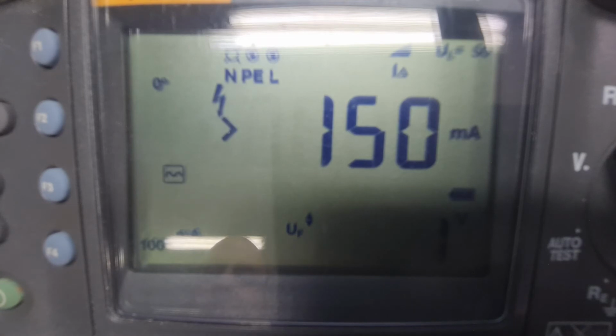So we can see that there is a significant difference in the performance of this RCD for type AC currents, which it was originally designed and sold for, with respect to DC leakage currents. Obviously, at the time, no appliances produced DC leakage currents, and therefore there was not the need for such protection. However, today we still find this type of RCD, especially in old properties which have not been renovated for some time, and as we can see, it practically has no protection for DC ripple leakage currents. I am going to continue testing.